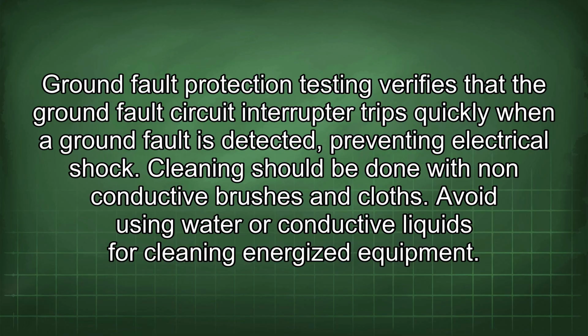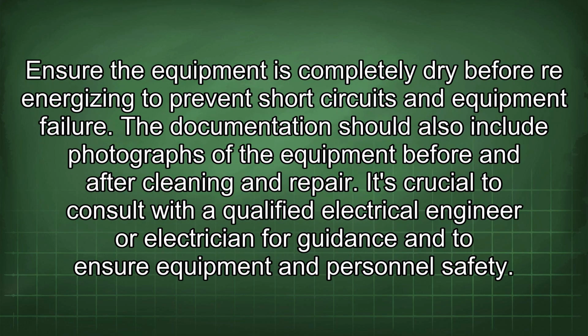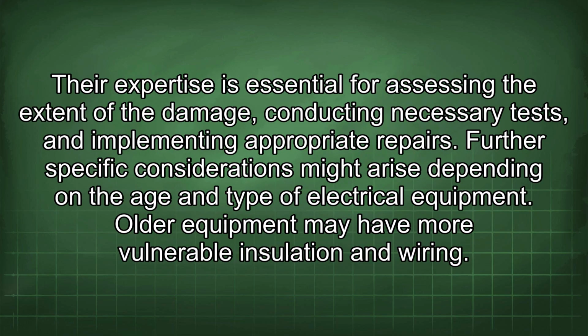Avoid using water or conductive liquids for cleaning energized equipment. Ensure the equipment is completely dry before re-energizing to prevent short circuits and equipment failure. The documentation should also include photographs of the equipment before and after cleaning and repair. It's crucial to consult with a qualified electrical engineer or electrician for guidance and to ensure equipment and personnel safety. Their expertise is essential for assessing the extent of the damage, conducting necessary tests, and implementing appropriate repairs.